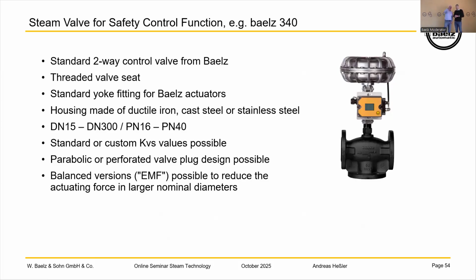If I remember correctly, this picture shows a control valve with a positioner. Correct. But in the normal case, you can have an electric actuator on it, for example with safety positions, or you put a solenoid valve on it. That's just a picture of the 340. To be absolutely correct, the 340 steam valve is just used for safety purposes. When there's over temperature on the secondary side, the steam valve closes, and it has no control function because the whole control function is on the condensate. When we do a condensate control, correct. When we do a steam control, we will use this kind of valve with this positioner. But if we do the standard BAELZ configuration, it's condensate control. Correct.